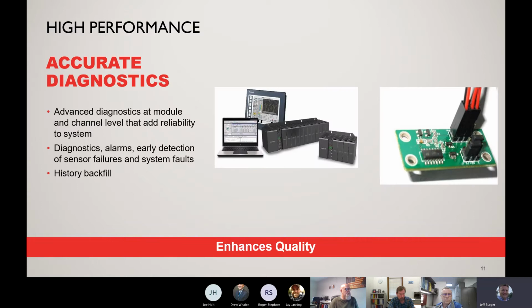We talked a little bit about the diagnostics that are on board on this HC900. As I stated earlier, the diagnostics go all the way down to the board level, and it shares that information through either the configuration software or through the display that you have hooked up to the I/O rack. This will allow you early detection of sensors that are going to fail. For example, with thermocouples, the detection system will sense if there's a failure that's about to occur but hasn't occurred yet, and this will save you a lot of downtime, because you can replace your thermocouple before it actually fails.